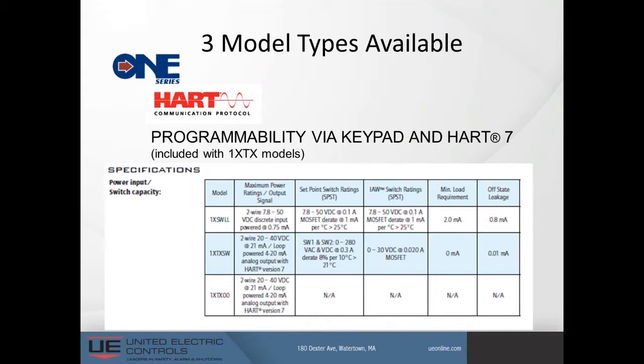That first device is for anything that's going to be interfaced with a PLC or DCS, where all you want to do is switch to a discrete I/O. That's your product. That will get it done. It's the same two wires that the mechanical switch was connected to. Take those two wires off, put this in, wire them up to the terminal block, and it's up and running. So it is also, keep in mind, still an optically isolated device. Again, it's going to work just like the switch did. Now, we've improved our capabilities by offering HART.